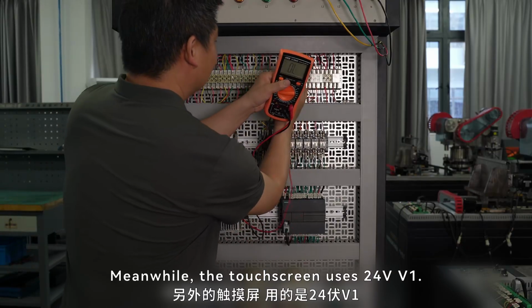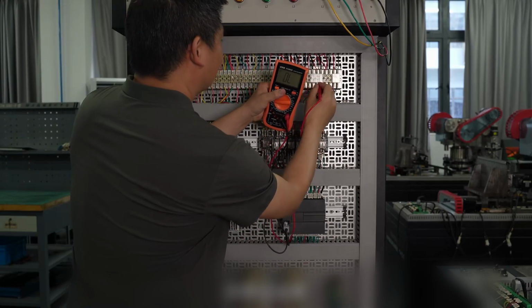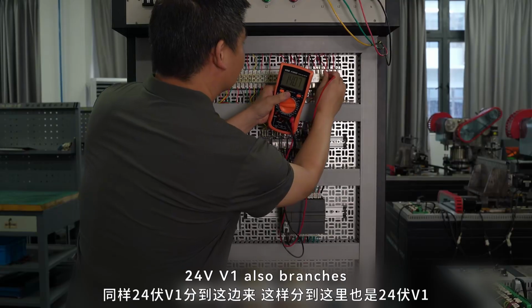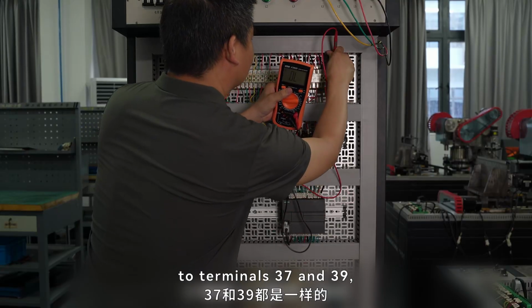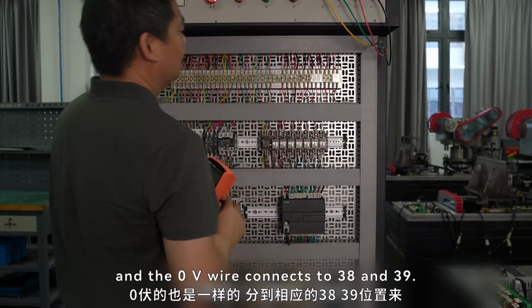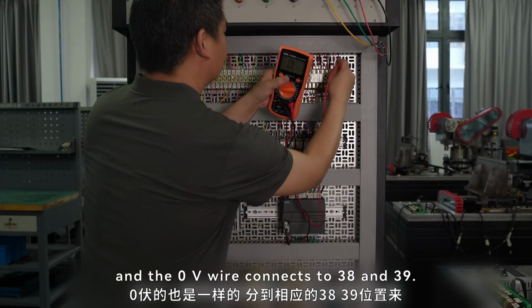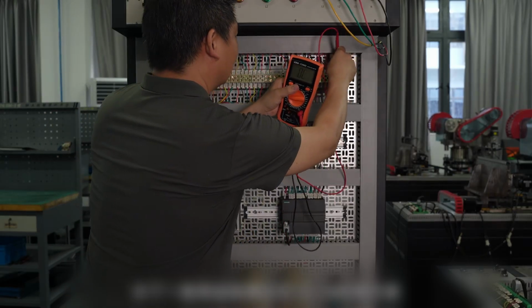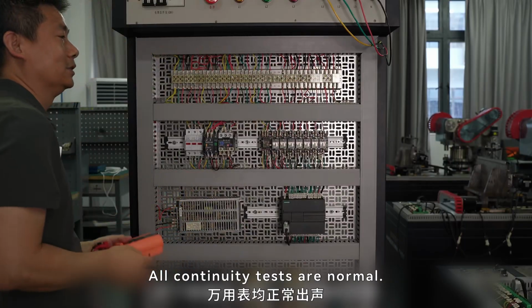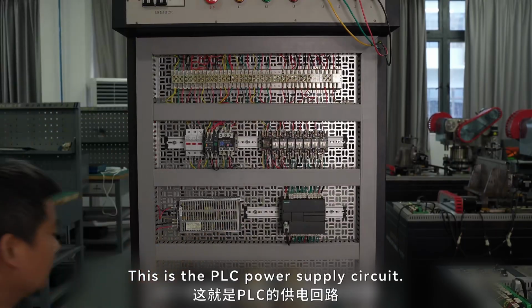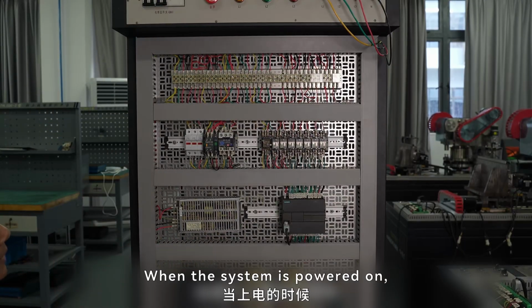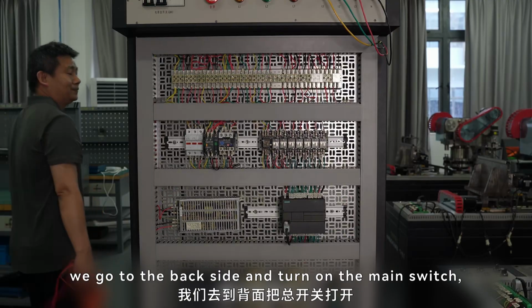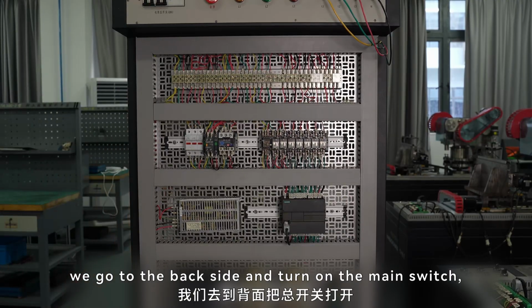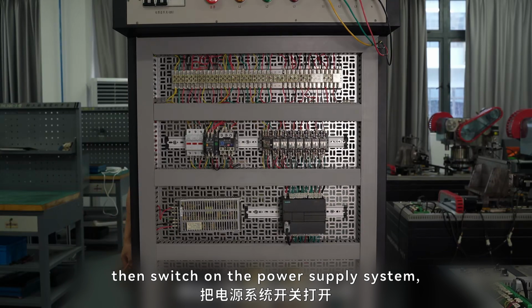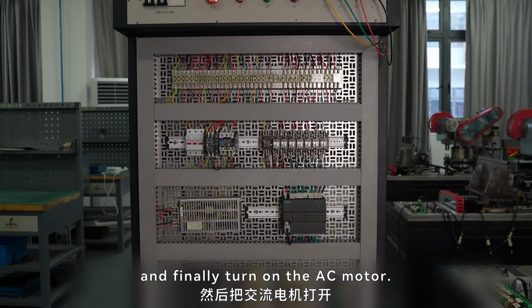Meanwhile, the touchscreen uses 24 volts V1. 24 volts V1 also branches to terminals 37 and 39, and the 0 volts wire connects to 38 and 39. All continuity tests are normal. This is the PLC power supply circuit. When the system is powered on, we go to the backside and turn on the main switch, then switch on the power supply system, and finally turn on the AC motor.